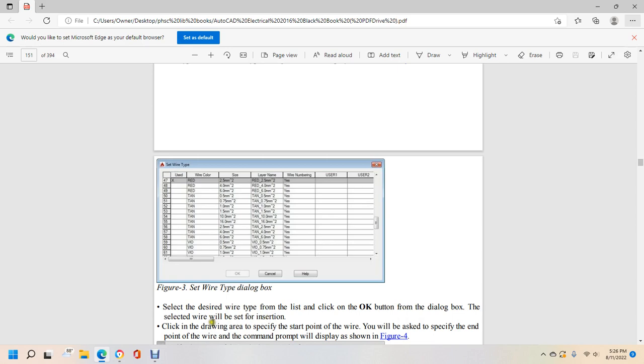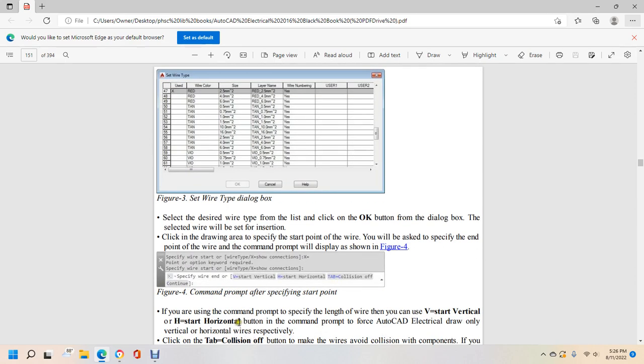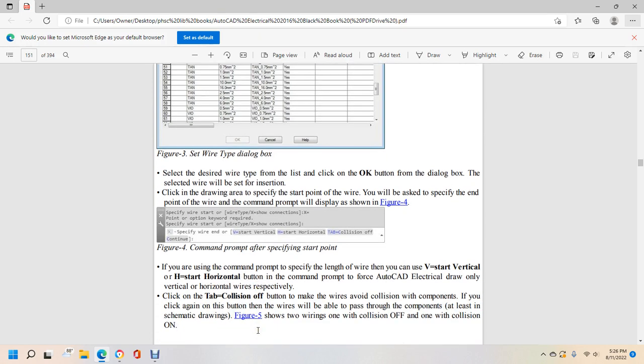Select the wire type from the list and click OK. Then select the wire set for insertion and check the drawing area. The start point of the wire will be requested, then specify the endpoint. You can use V for vertical or H for horizontal direction. The collision option, when toggled on, makes wires avoid collisions with components. When clicked again, the wire will be able to pass through components. Figure 5 shows two wires, one with collision off and one with collision on.